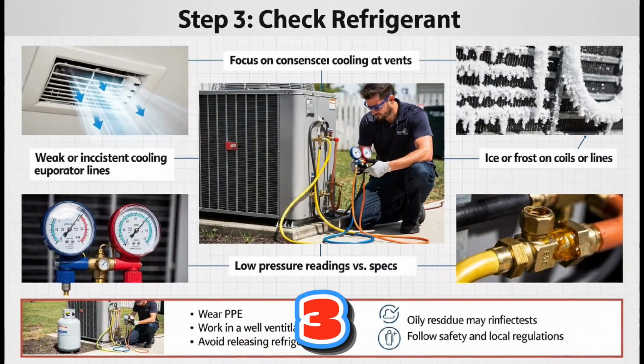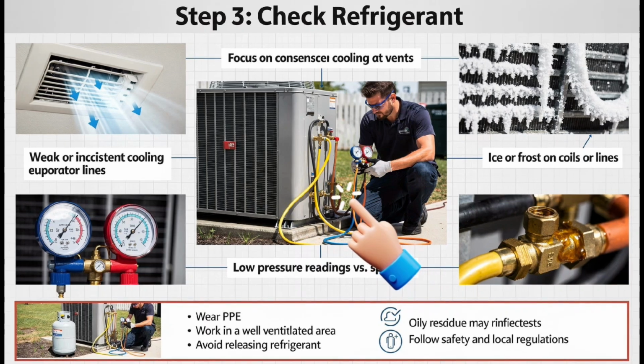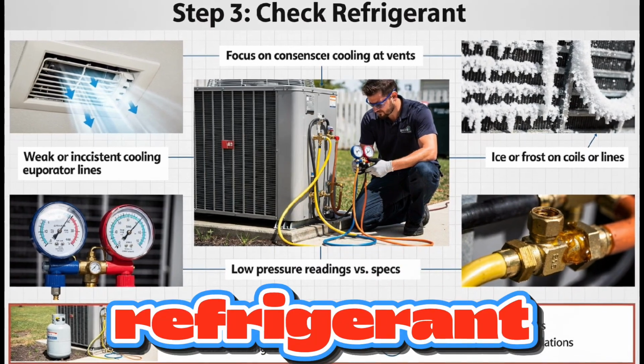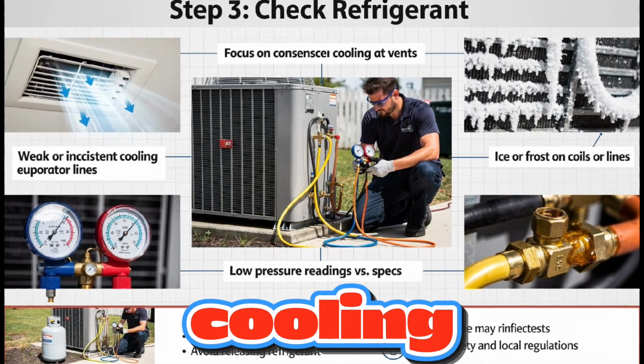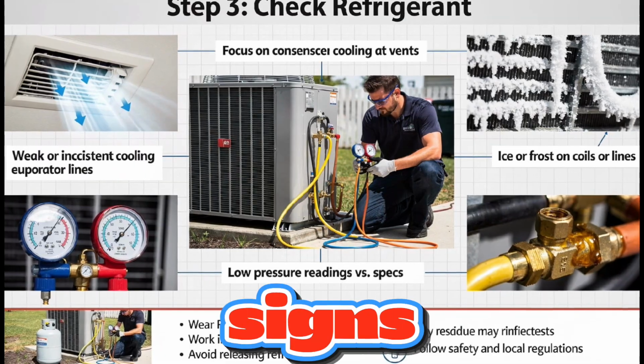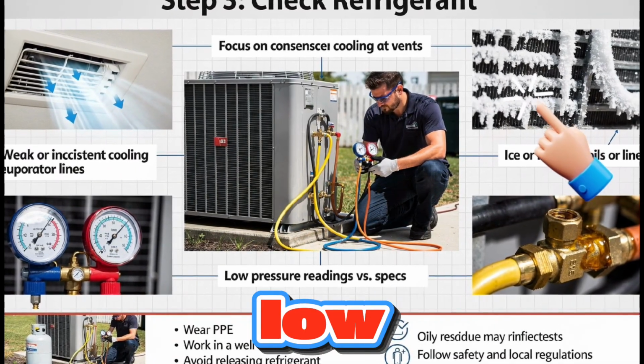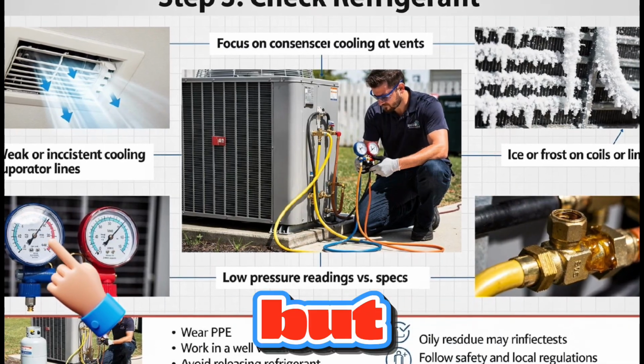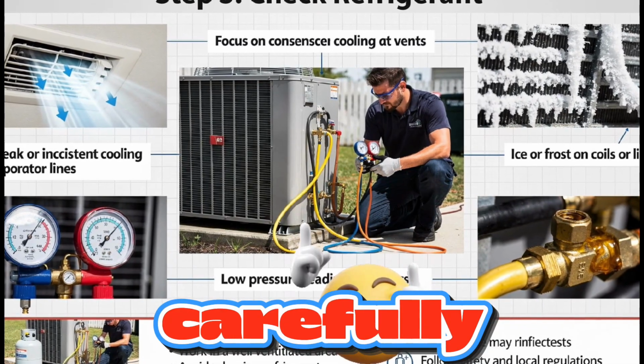Step 3: Check refrigerant. Now move to refrigerant. Low refrigerant means poor cooling performance. Look for signs like weak cooling, ice formation, and low pressure readings. But always handle refrigerant carefully and follow safety guidelines.